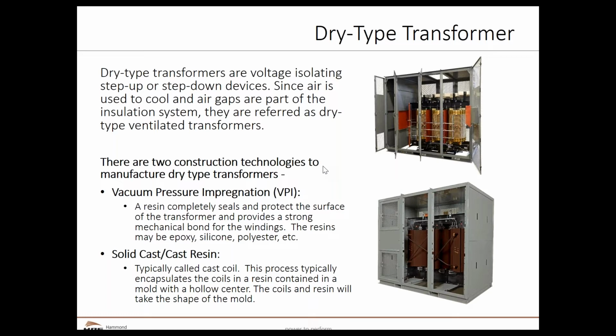With a vacuum pressure impregnation transformer, the coils are submerged into a vat. The vat has a vacuum pulled in it, so there are no air bubbles. Then we use the vacuum to submerge the transformer in the liquid varnish. We'll call it generic varnish, but it's nothing to do with the varnishes you would put on furniture, for instance. The transformer coil is fully submerged, and then the vessel is pressurized to further push that liquid into it. And there might be 2 or 3 or 4 or more coatings of that put on.